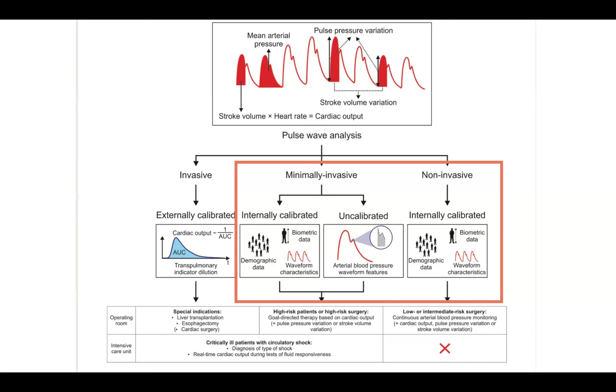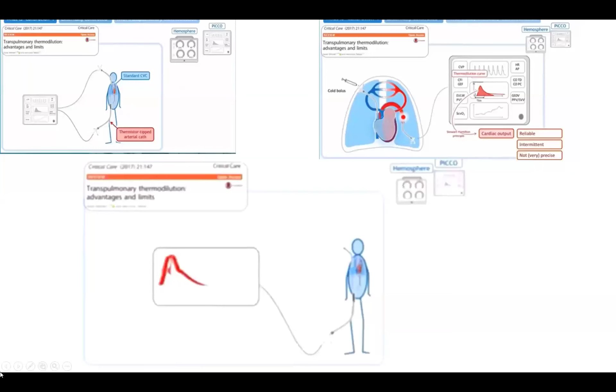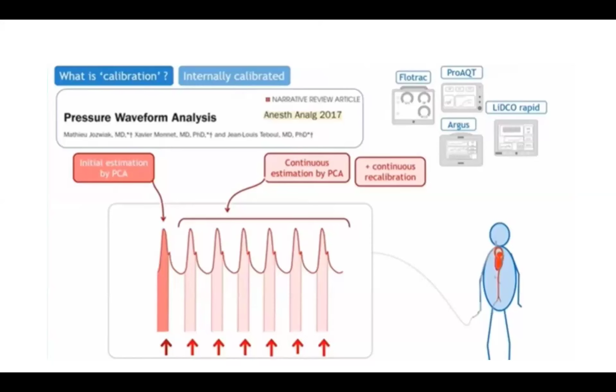Unlike the externally calibrated invasive method, which uses pulse contour analysis with external calibration using thermodilution techniques, the non-calibrated pulse contour analysis devices either use internal calibration, consisting of initial estimation of pulse contour analysis using demographics, biometric data, or waveform characteristics, or incorporating echo-derived stroke volume, followed by continuous estimation of pulse contour analysis and continuous recalibration.